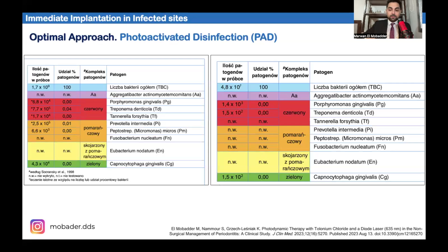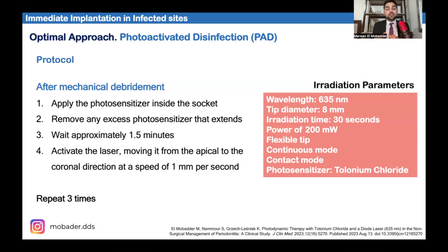So, this is the protocol. These are the irradiation parameters. As I've said, these parameters were calculated. Today, unfortunately, we don't have time to explain in detail why we have chosen these parameters. The protocol is basically to apply the photosensitizer inside the socket, remove the excess of the photosensitizer, wait almost 1.5 minutes, because we want to have a deep penetration of the photosensitizer, and then activate the photosensitizer with the laser with a dedicated special tip, and this will result in a release of reactive oxygen species.